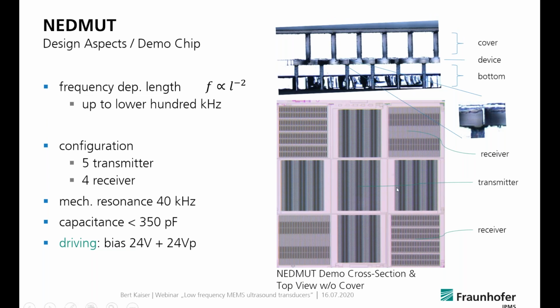These very first devices have a mechanical resonance of 40 kilohertz and an electrical capacitance of below 350 picofarad, and they are driven by a bias voltage of 24 volts plus an alternating signal of 24 volt peak. What happens with this driving is the movement of the actuators, and I included a cross-sectional view here. You see this is from an actual specimen. This is cut, and we have this microscope picture here, so you see the inlets and outlets, if you want, in the cover and bottom wafer.